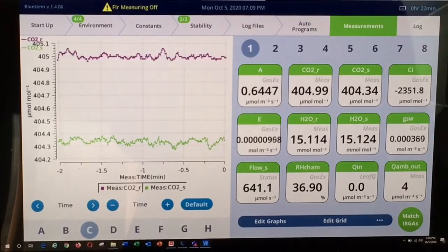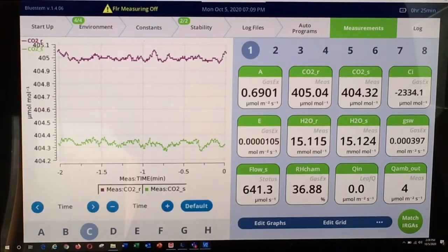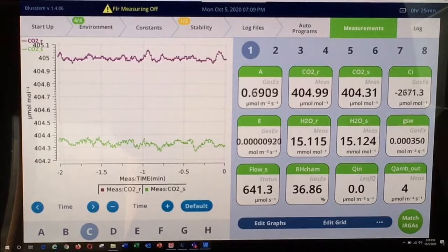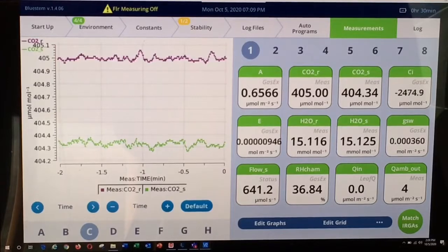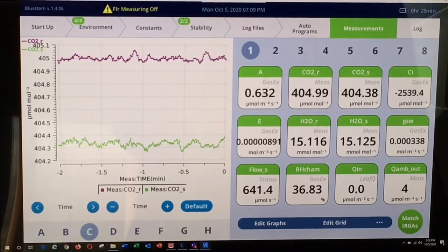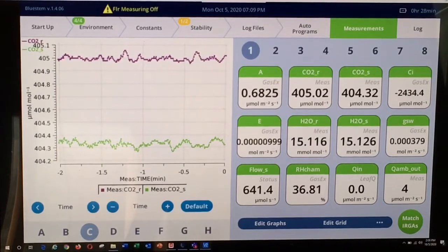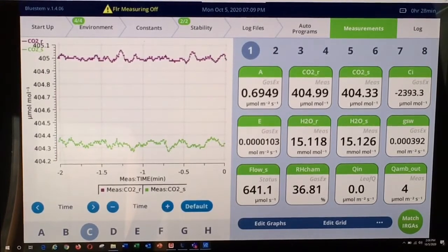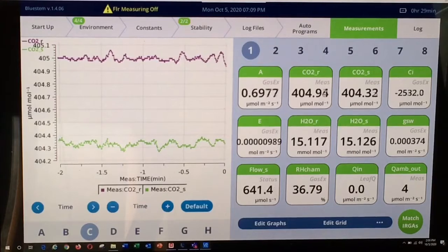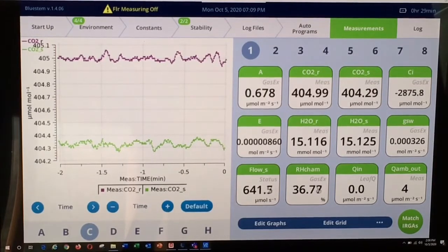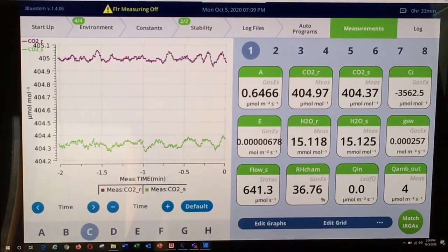Range matching is a new feature that LI-COR introduced to the LI-6800 starting with version 1.4.02 of the software. From that version on, users may occasionally experience a message that occurs during the system and warm-up tests that advises them that they may need to check or conduct a range match. Range matching allows the matching functionality between the reference and sample IRGAs to be mapped as a function of CO2 sample concentration. That data can then be fit using a curve, allowing the instrument to continuously match at whatever concentration it happens to be operating at.